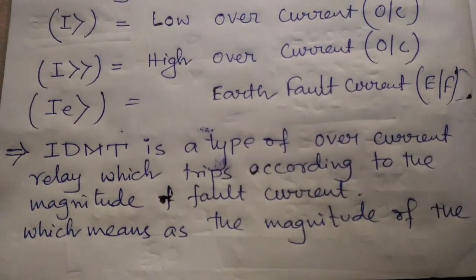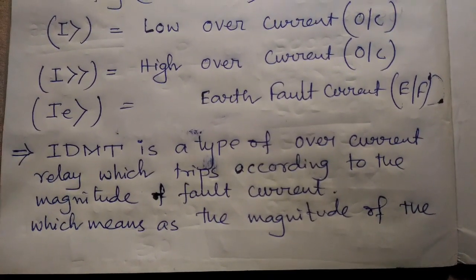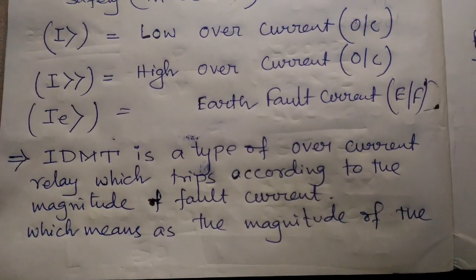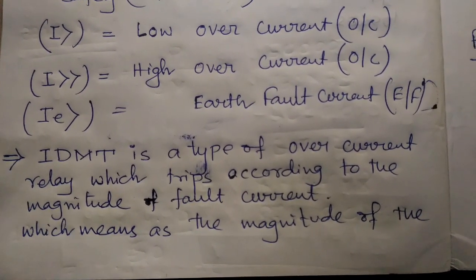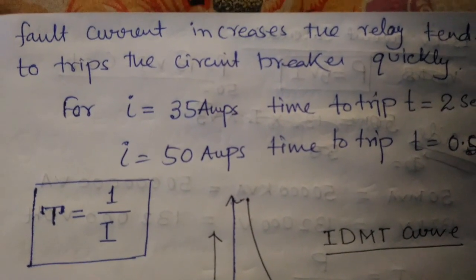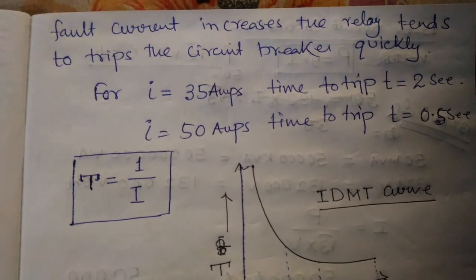What is IDMT? IDMT is a type of overcurrent relay which trips according to the magnitude of the fault current. This means as the magnitude of fault current increases, the relay tends to trip the circuit breaker quickly.